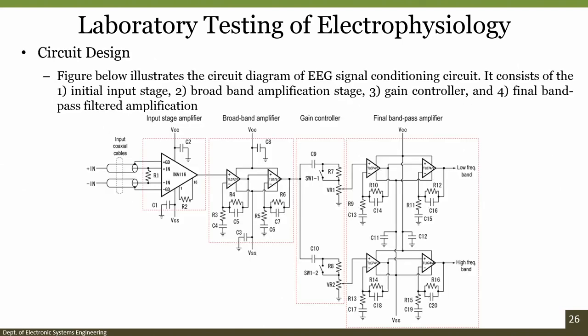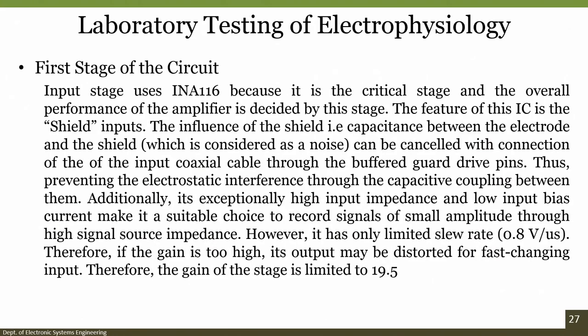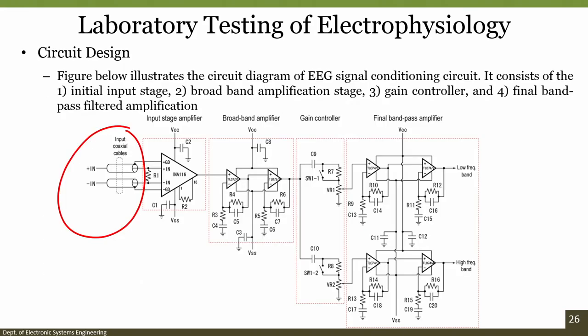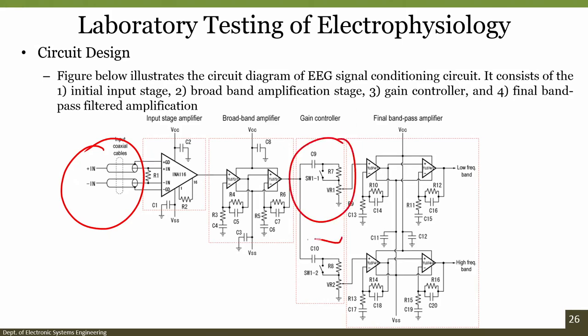You see here the circuit design, and before even the first stage, there are coaxial cables, very important, so that it will filter out the noise. And the role of coaxial cable or shielded inputs is that the capacitance between the electrodes and the shield can be cancelled. So, the help of this coaxial cable is significant. Here, the electrodes are connected to the first stage, which is your input stage amplifier, and then there is a broadband amplification. This will further amplify the signal. You can control the gain using either this one or this circuit, depending on what kind of signal you are processing. And finally, there is a band pass filter amplification, which you can see as a 4-stage.